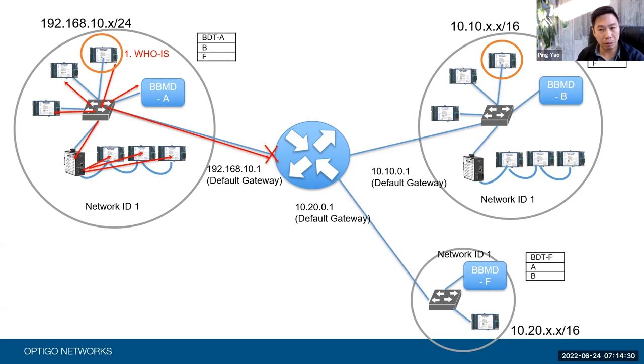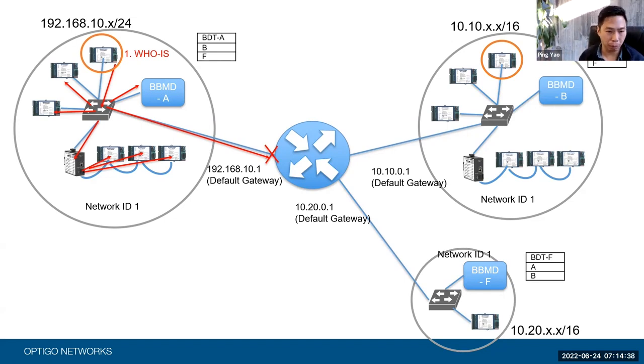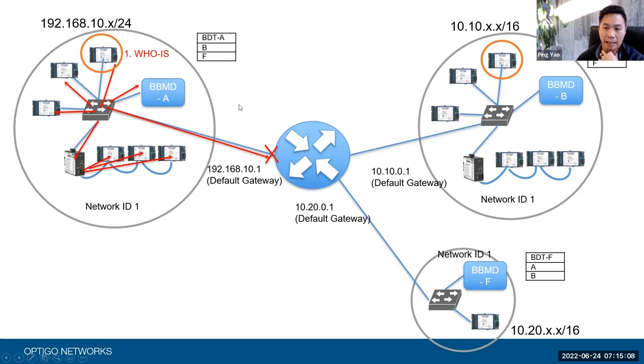That's where the BBMD comes into play. A BBMD is most of the time not a separate device — most of you have probably noticed that. It's just a function of another BACnet IP device. You see how this WhoIs hits every device in its subnet, including the device that's marked as a BBMD. We're going to call it BBMD-A.